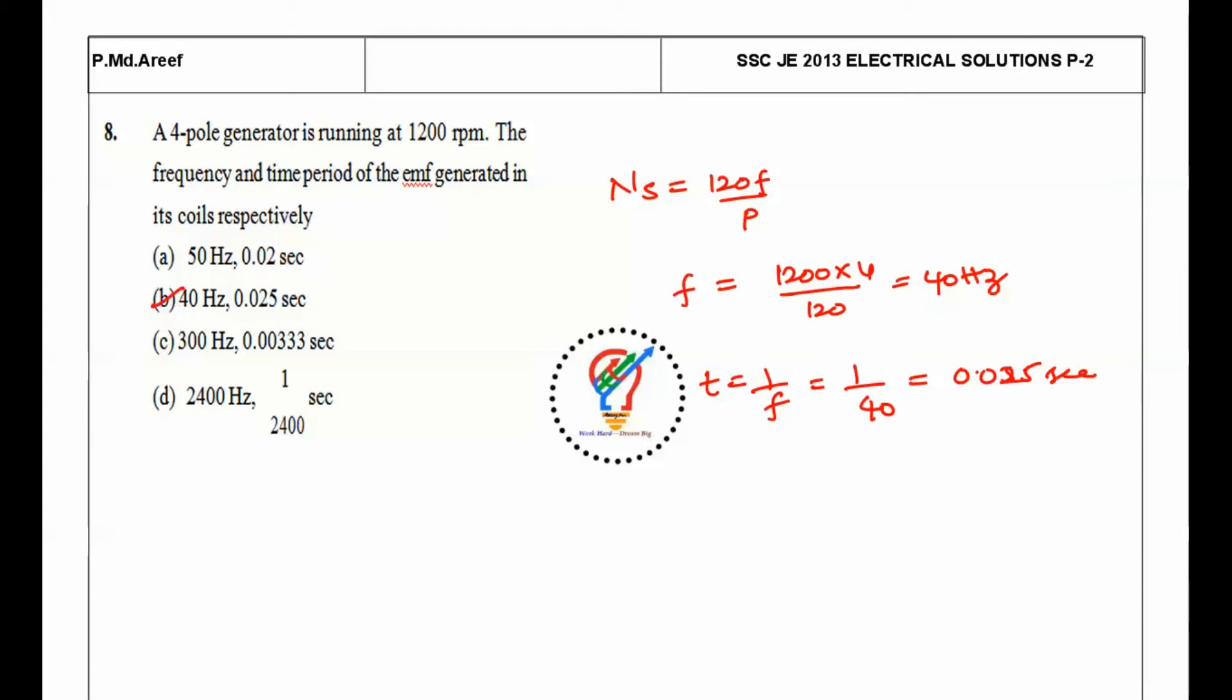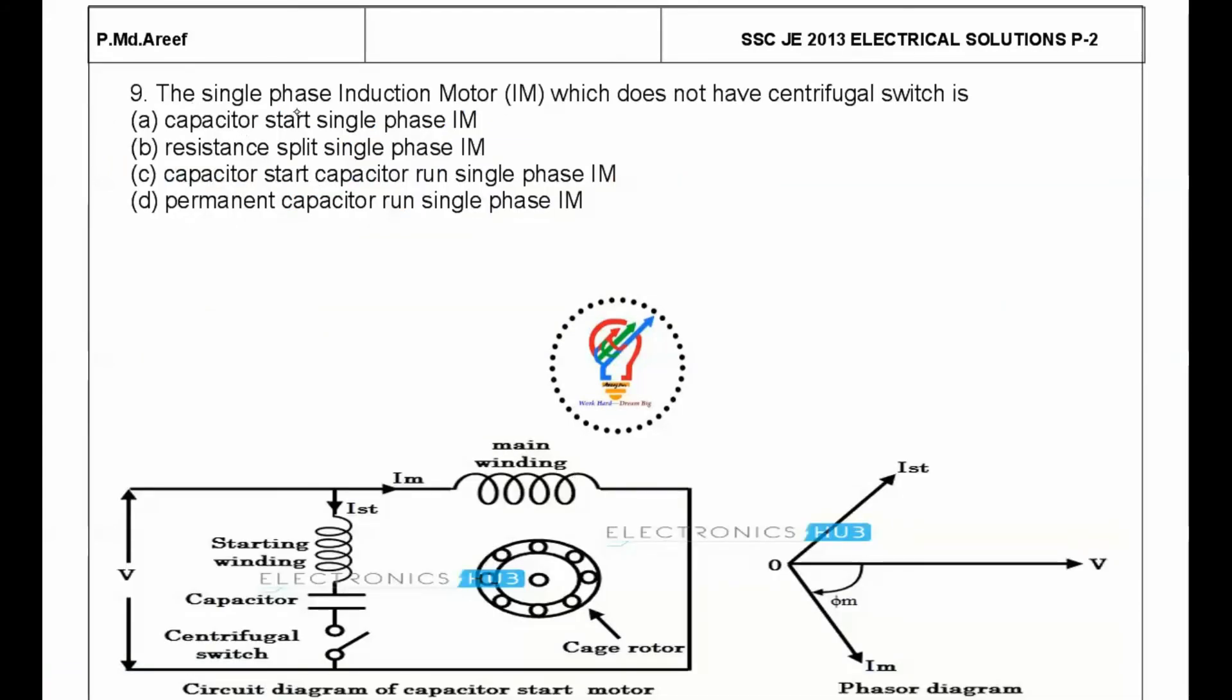Next question: the single-phase induction motor which does not have a centrifugal switch. Here's the circuit diagram for a capacitor start and capacitor run motor. When the centrifugal switch is not there, it's permanently connected. Once it is permanently connected, it acts as a permanent capacitor run single-phase induction motor. Here we are connecting the capacitor to create the phase difference between the main winding and starting winding.